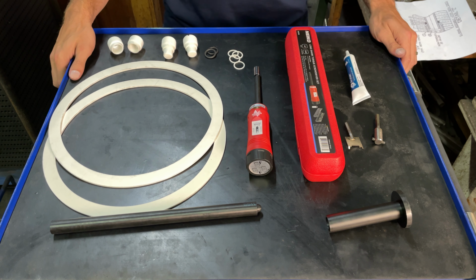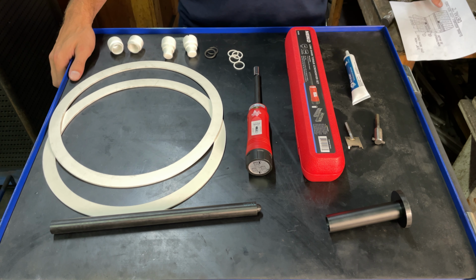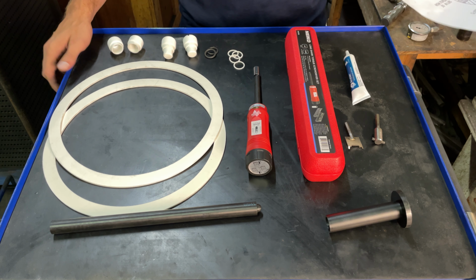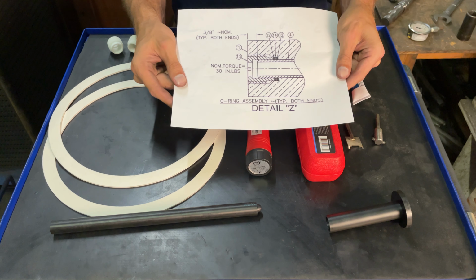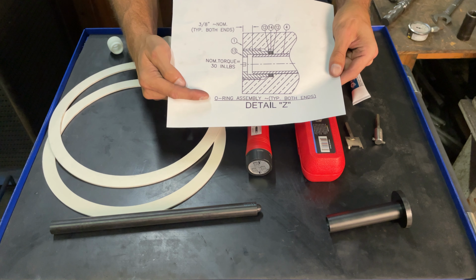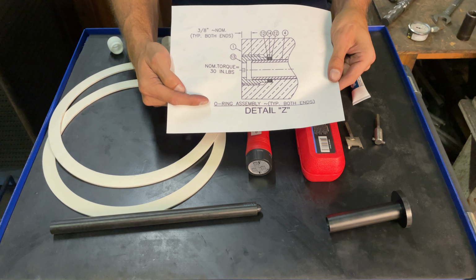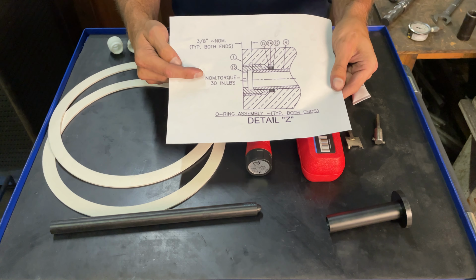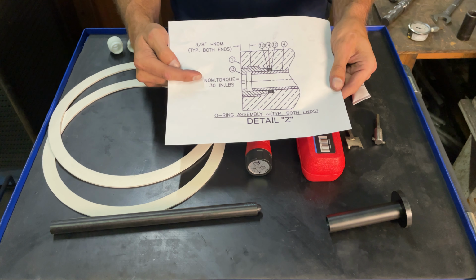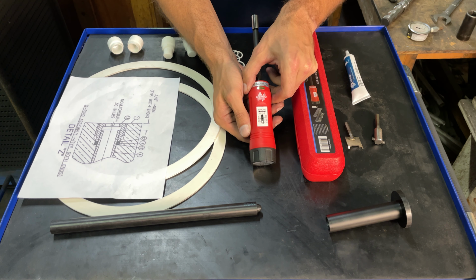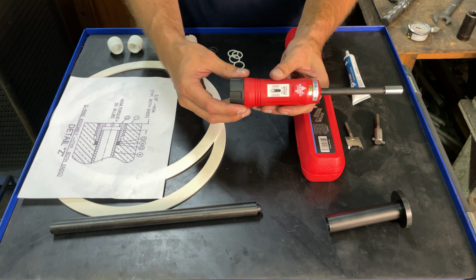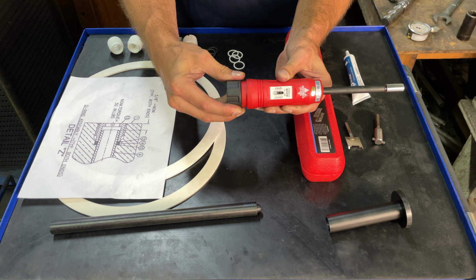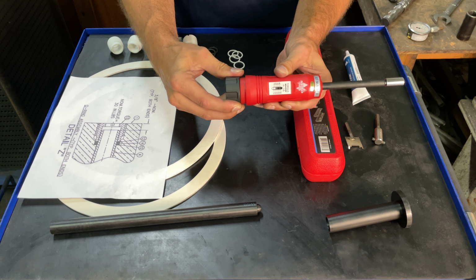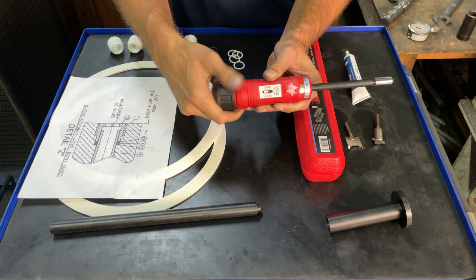When setting up the torque screwdriver, you will find the torque requirement on the assembly drawing. On the assembly drawing, you will notice a blow-up detail of the O-ring assembly. In this case, the nominal torque is 30 inch-pounds, but it will be specific to your heat exchanger. To adjust the torque setting on the screwdriver, pull the lower end cap and rotate until the red line on the gauge lines up with the required torque setting on your assembly drawing.